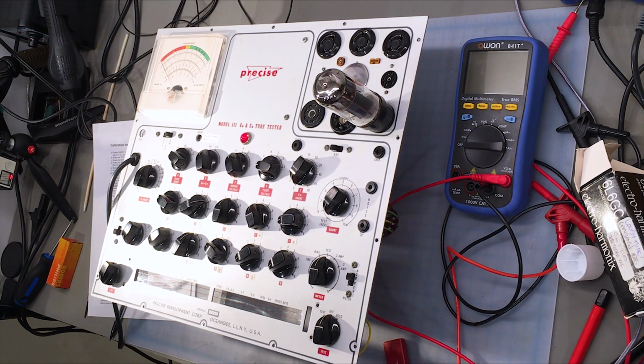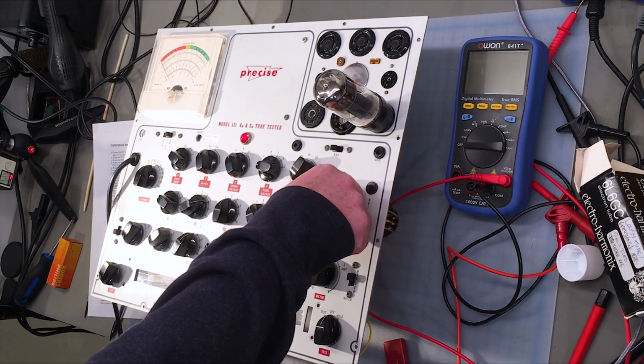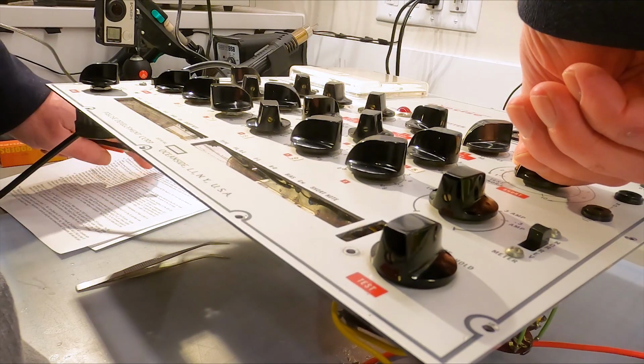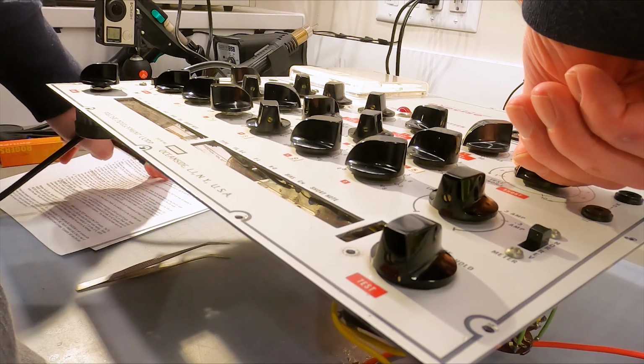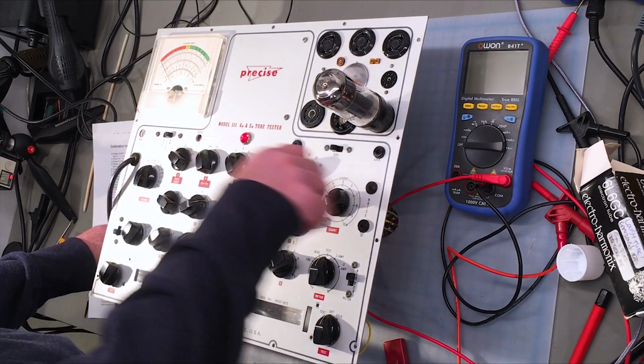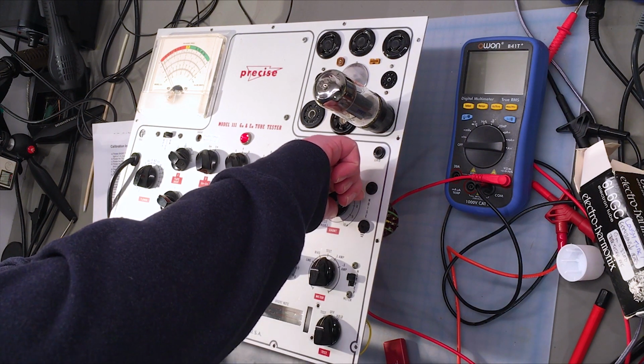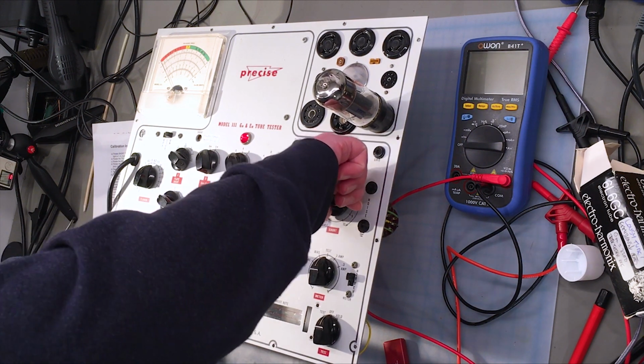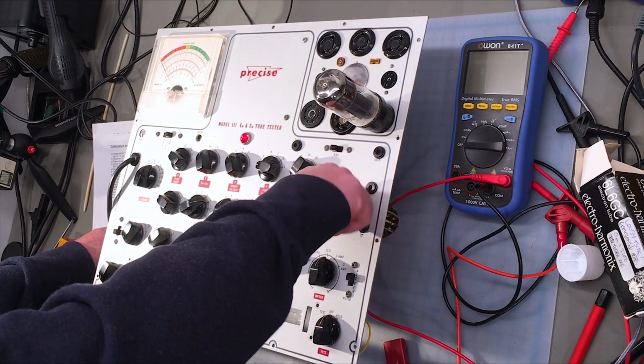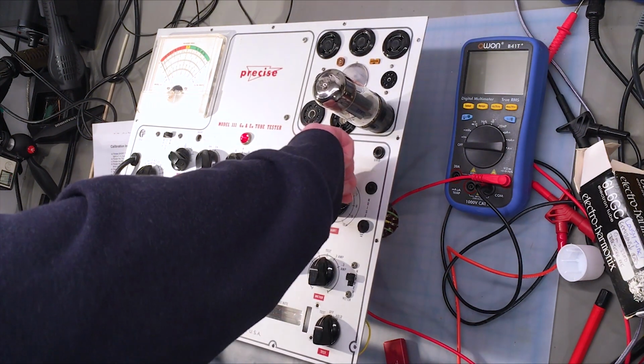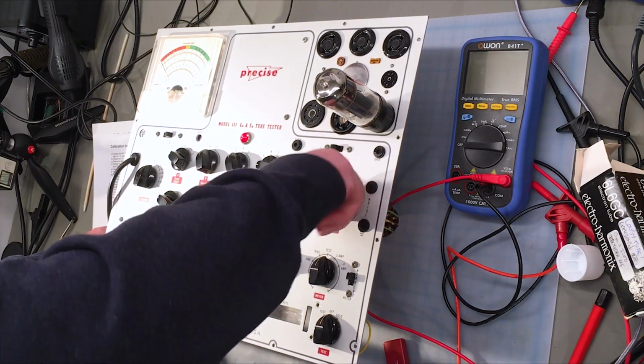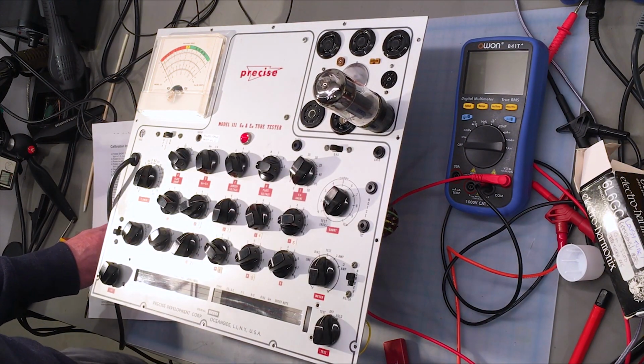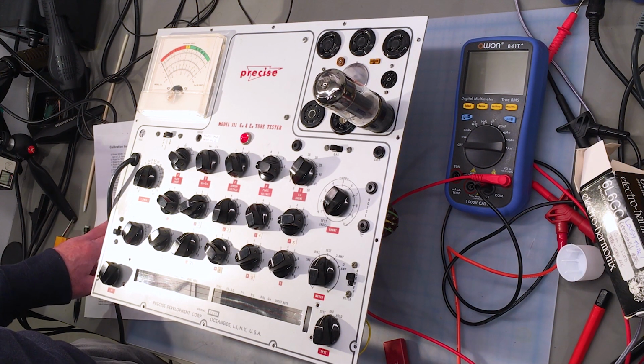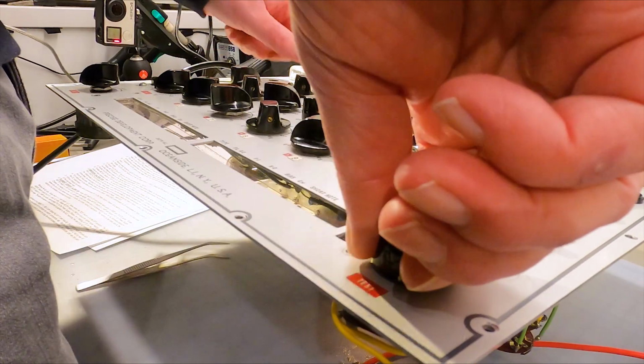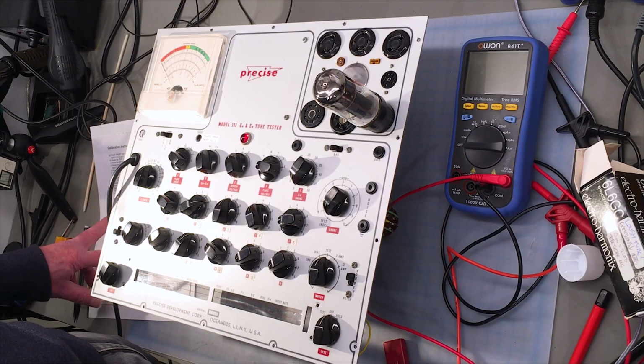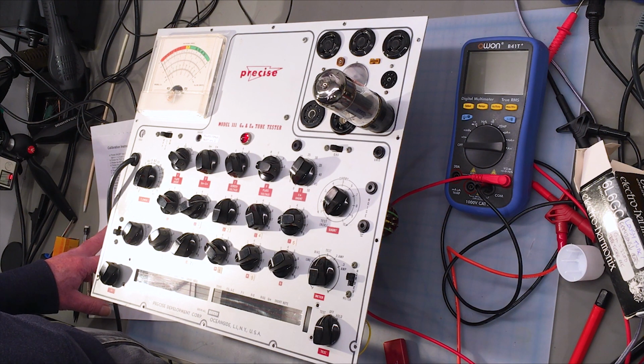Turn the instrument to the on position and we wait for the tube to heat up. We'll do the short test where we should see a short on position 2 and 7. We know that we should see in addition a short on 1 in this particular instrument, and we see one on 2, it goes out on 3, 4, 5, 6, 7, we see it again on 8, 9, and 10. Coming back, we see it again on 1. Bring it back to test, return the test switch to off and turn the instrument off.